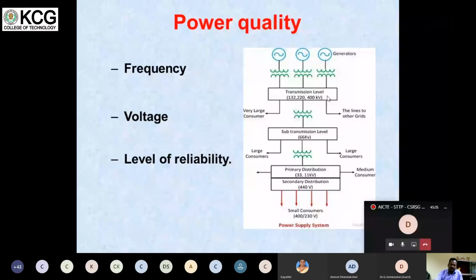So why? Because when we allow more voltage variation at the higher voltage side, using a transformer tap changer, etc., we can increase the voltage. Or using some other FACTS devices, we can increase the voltage when it is reaching the consumer end. That is why deviation at the higher voltage is allowed more, and deviation at the lower side, that is 230 volt and commercial 440 volt 3-phase system, is very less. It is only plus or minus 6%. When you go for higher voltage, it is allowed up to 9% or 10% also. The reason is voltage can be boosted up, but as far as frequency is concerned, it cannot be boosted up.